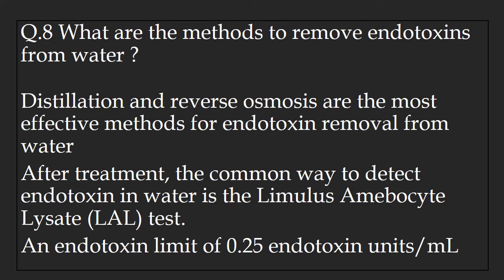Question number 8: What are the methods to remove endotoxins from water? Distillation and reverse osmosis are the most effective methods to remove endotoxins from water. After treatment, the common way to detect endotoxins in water is to perform the Limulus Amoebocyte Lysate (LAL) test. The endotoxin limit of WFI as per USP is 0.25 endotoxin units per ml.